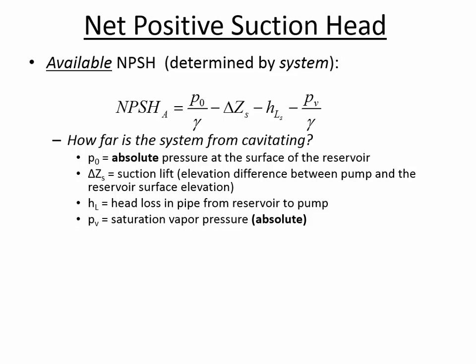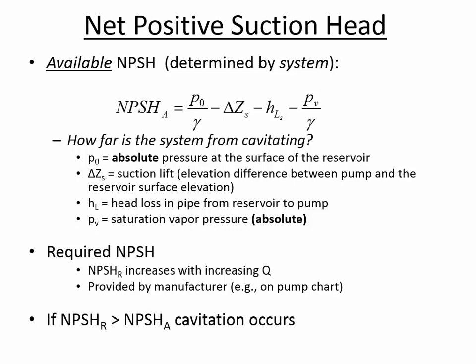Yeah. What you would need to do is you'd need to do this check to make sure that the available NPSH, you want the available NPSH to be bigger than what's required. You want to give the pump the suction head that it requires to prevent cavitation. And usually it's not an issue. You'll be able to put the pump somewhere close to the origin reservoir, or make sure that it is below the liquid surface.